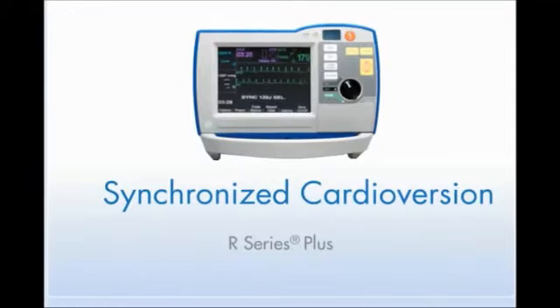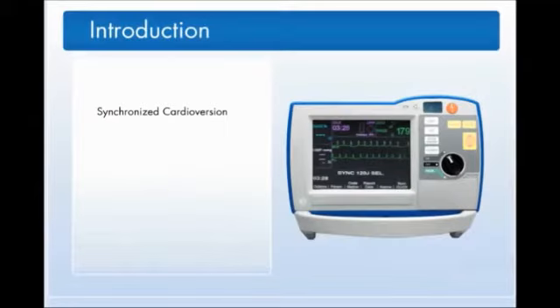Welcome to the R Series Synchronized Cardioversion module. Certain arrhythmias, such as ventricular tachycardia, atrial fibrillation, and atrial flutter, require synchronizing the defibrillation discharge with the ECG R wave to avoid the induction of ventricular fibrillation. In this case, a synchronization circuit within the defibrillator detects the patient's R waves. When you shock the patient, the device discharges with the next detected R wave, thus avoiding the vulnerable T wave segment of the cardiac cycle.